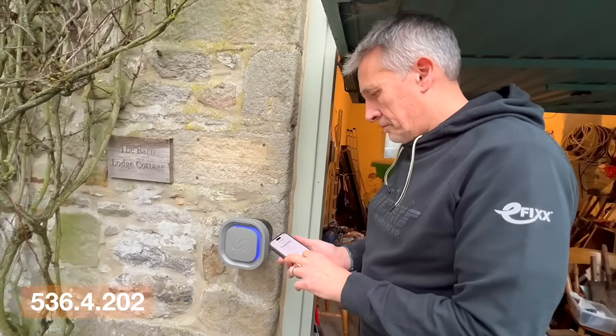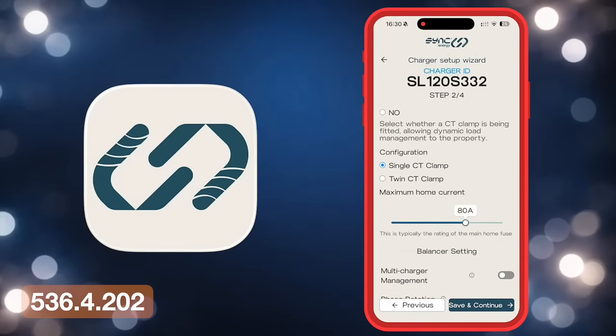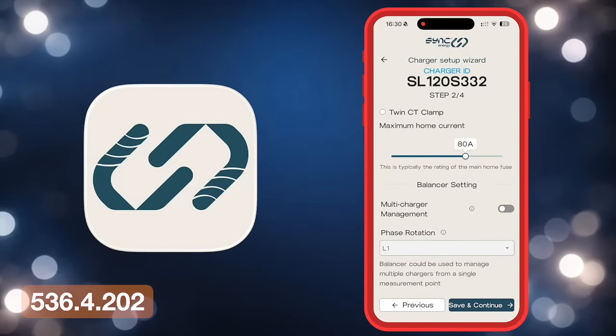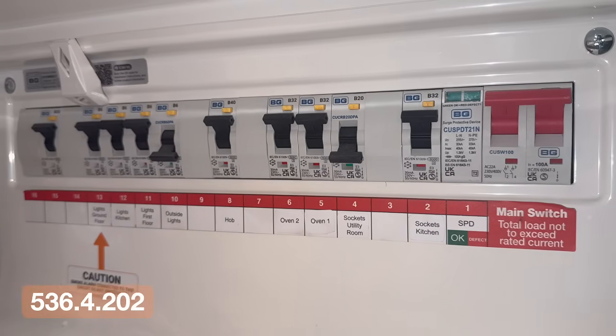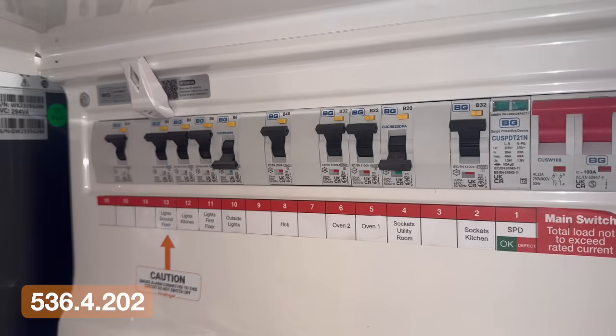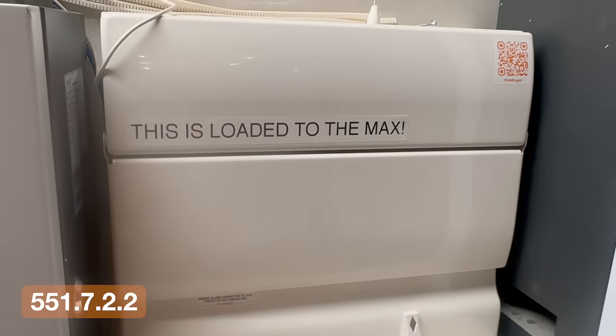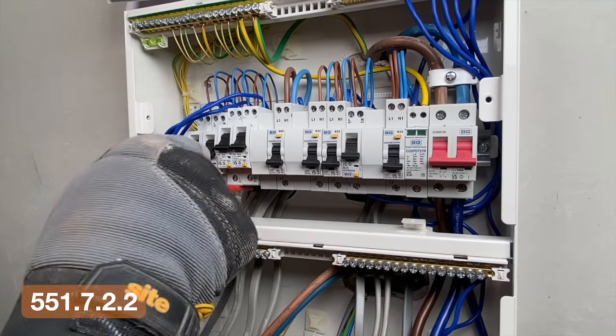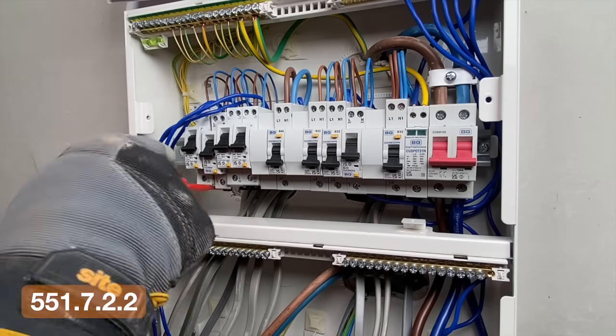If load curtailment is being used, it must reliably limit the current to within the rating of the assembly, and diversity cannot be used as a substitute for that control. There is also a practical implication here. If total connected load is being used as a method of compliance, the regulations require a warning notice, clearly stating the maximum permitted load for that assembly. So anybody working on it understands that limit before adding to the installation.